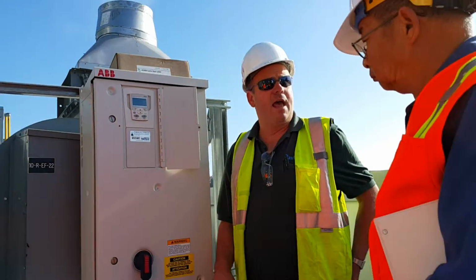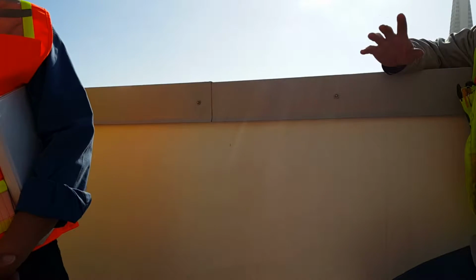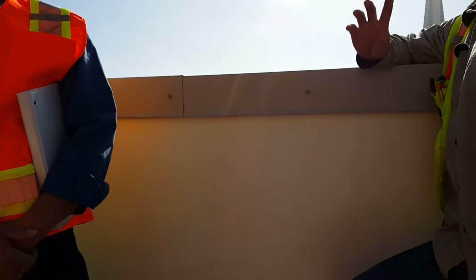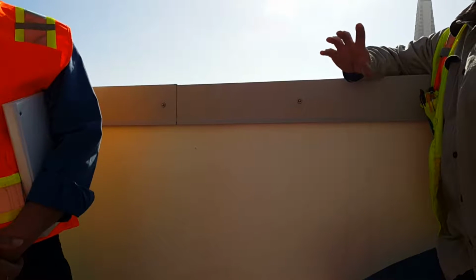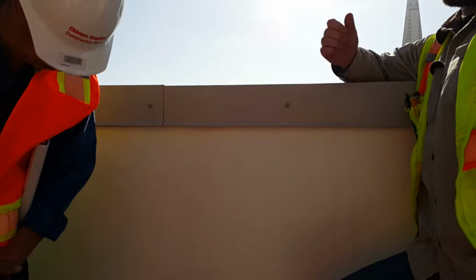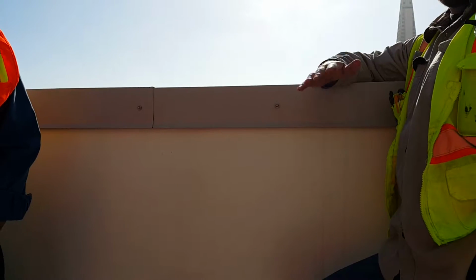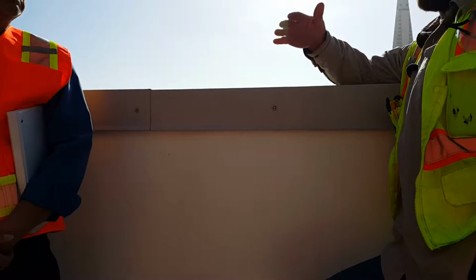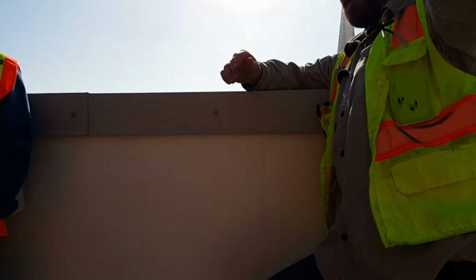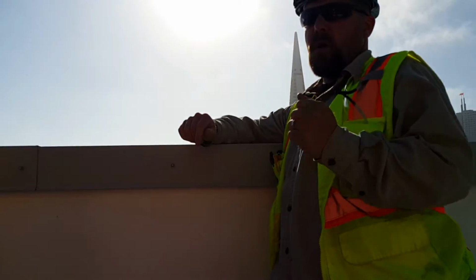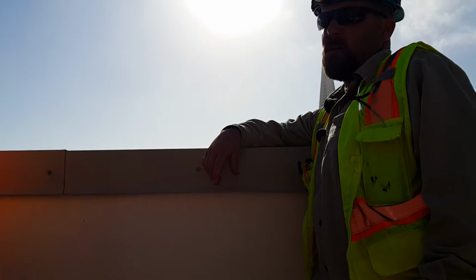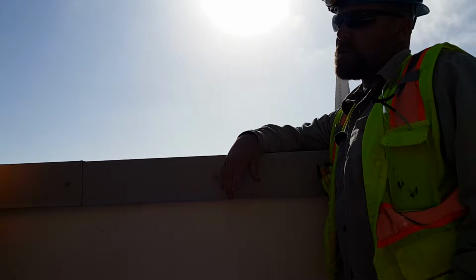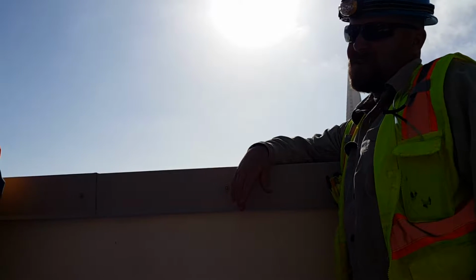That's right. Something else to mention is a lot of the equipment in your facility have fans and pumps. Fans more than pumps have a local disconnect at the equipment. If for whatever reason those local disconnects get turned off and you're seeing your drive ramping up and nothing's happening, make sure the drive has settled out. It's not running at 60 hertz when you throw that local disconnect back on. You want to stop the drive before you turn that local disconnect back on. Correct. Otherwise, a stopped motor looks like a dead short.